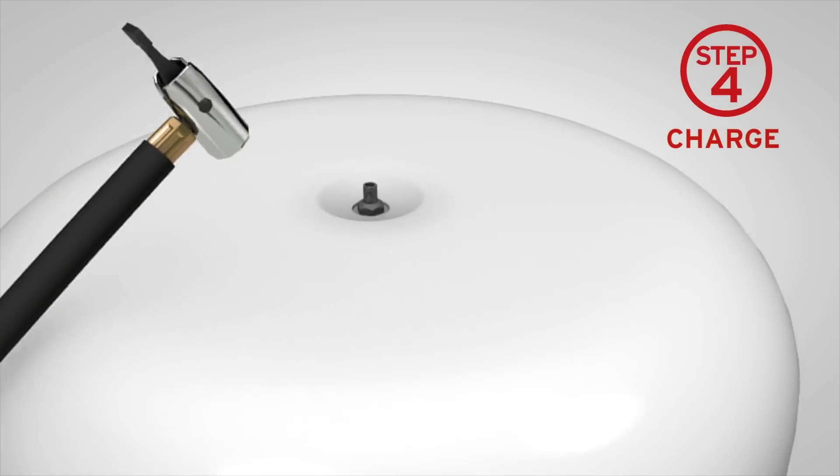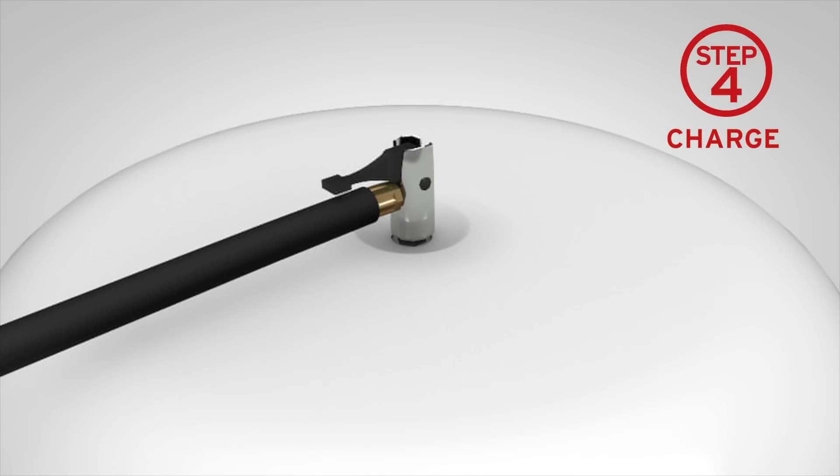To recharge the expansion vessel, simply connect a pump to the Schrader valve and inflate the vessel's internal rubber diaphragm until the pump's pressure gauge reads the correct pressure.